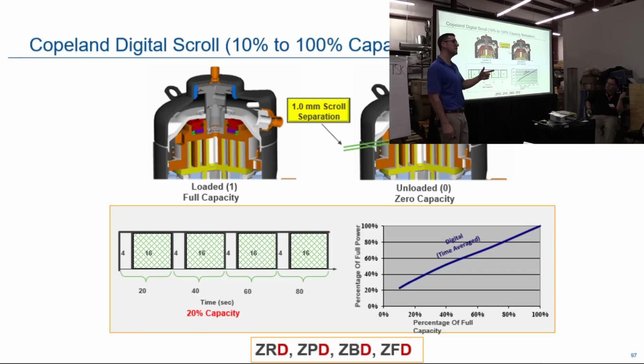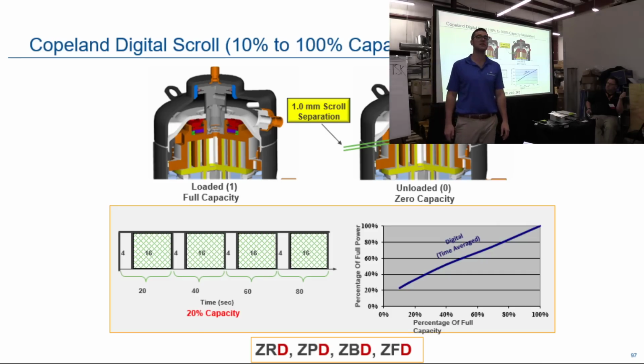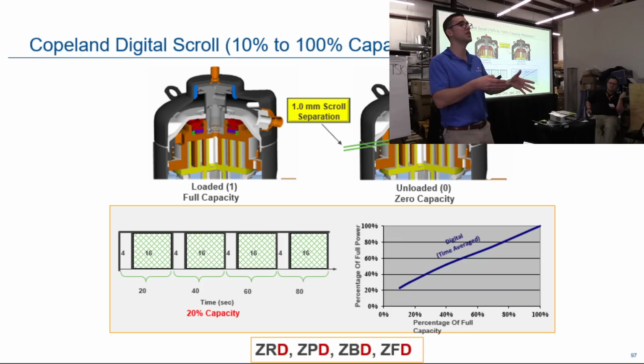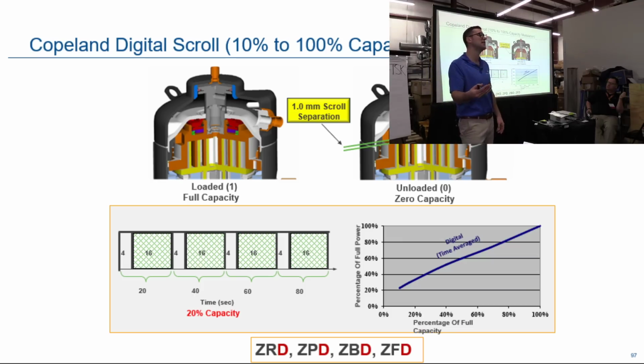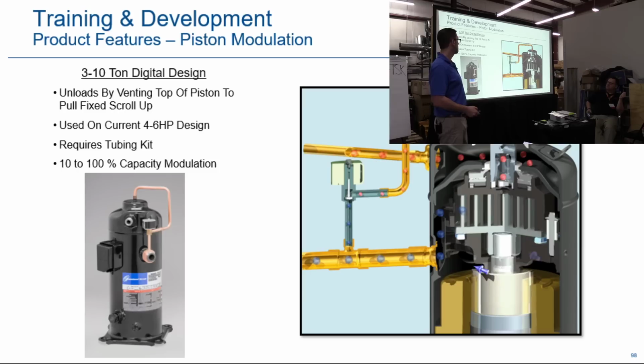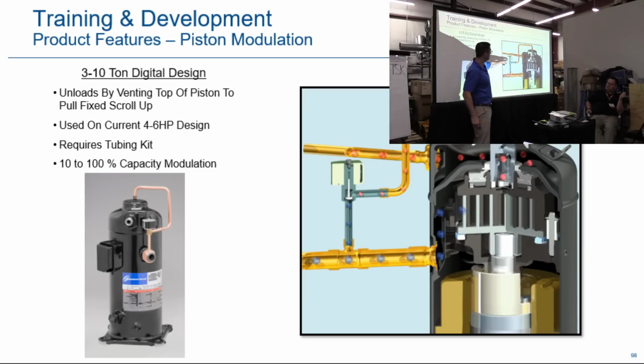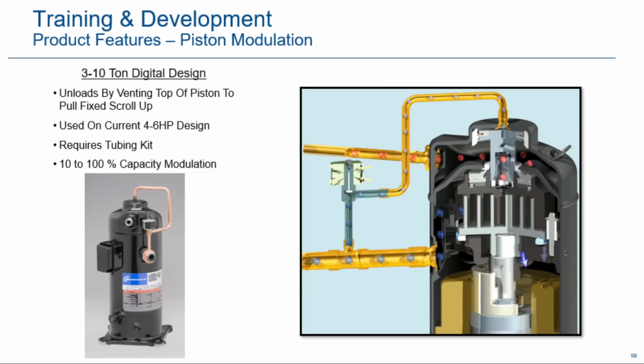How you can tell if it's a digital compressor: on the scrolls, the third character will be a D. Okay, that's how you tell if it's a digital. Really, when you look at it and you see a solenoid on the top or the side, you're going to know. This is how the digital works. When you see this solenoid activate, all of a sudden it'll bypass discharge gas and separate the scroll set, so there's no pumping action. So what you're hearing is the flanks touching each other as it's still spinning.